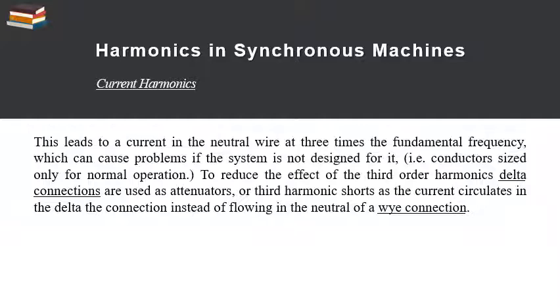To reduce the effect of the third order harmonics, delta connections are used as attenuators, or third harmonic shorting, as the current circulates in the delta connection instead of flowing in the neutral of a Y connection, meaning star connection.